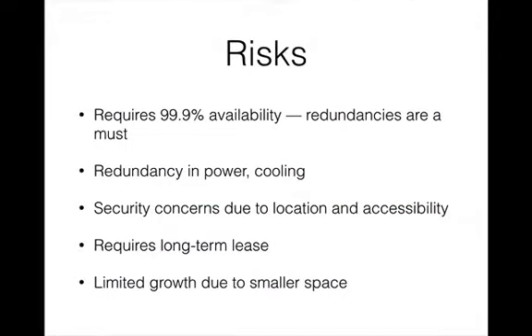There are many risks for this data center. The goal of achieving 99.9% availability requires that there is no more than 8 hours and 45 minutes of downtime during the year. Therefore, redundancy is absolutely necessary in this design, and without redundancy, it would be impossible to achieve that goal. There are risks of power failures, and this is addressed by having generators and redundant UPSs. Two separate and independent PDUs provide redundancies in power source. There are two separate air handlers, and a redundant cooling system provides redundancy to mitigate the risk of cooling failures.